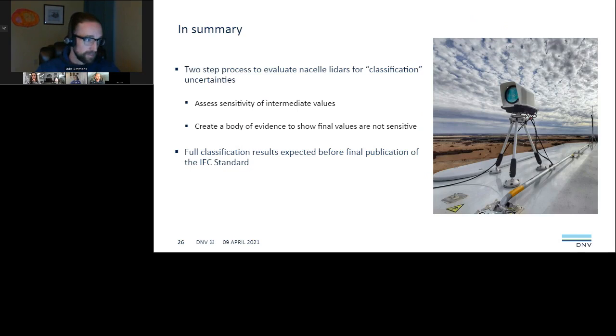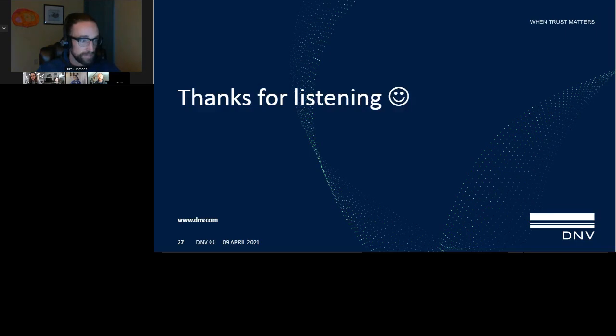So in summary, we've reviewed the two-step approach for nacelle LiDAR classification to consider how the measurement system and the algorithm are sensitive to changes in environmental conditions. And while we only had a glimpse of the data, the final results of the WindCube Nacelle LiDAR classification are underway, with delivery expected prior to publication of the IEC standard, allowing industry to hit the ground running using the WindCube Nacelle for both onshore or offshore power curve testing. So that's it for me, and I will pass it on to Alex and look forward to the questions.